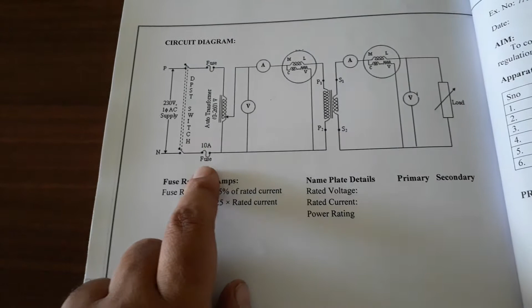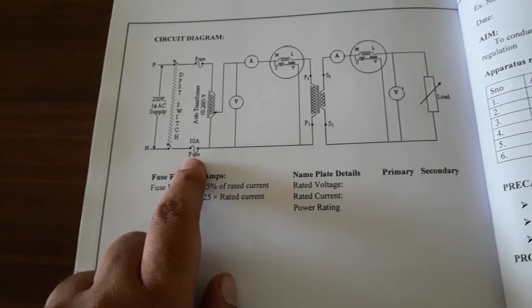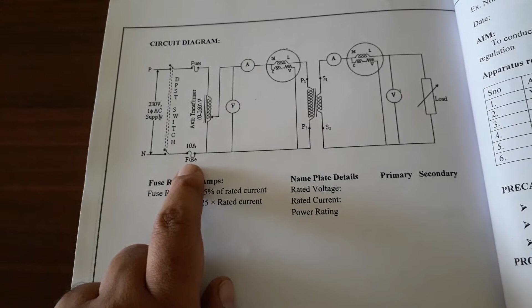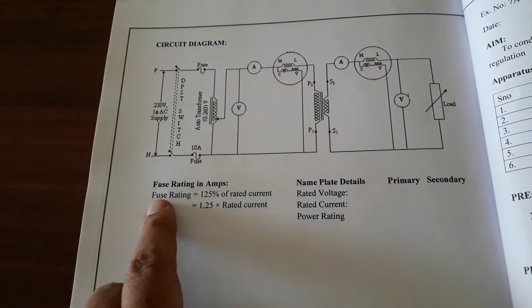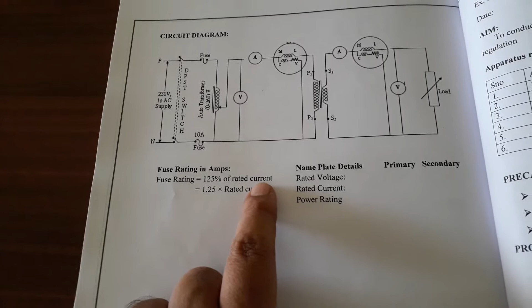How to fix the fuse rating? In our house also, due to an excess amount of load, the fuse will be blown out, so we rectify that problem with a new fuse wire. Similarly here also we have the fuse. And how to fix the fuse rating? It is 125% of the rated current.